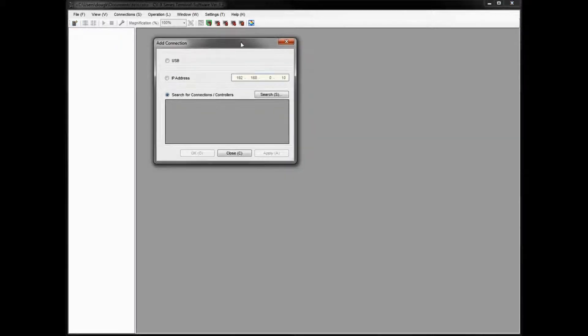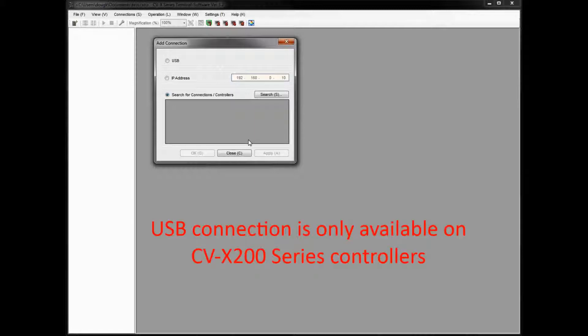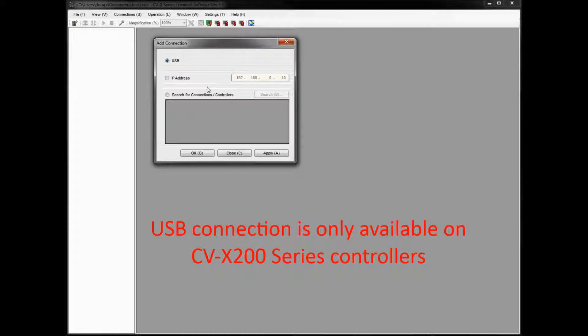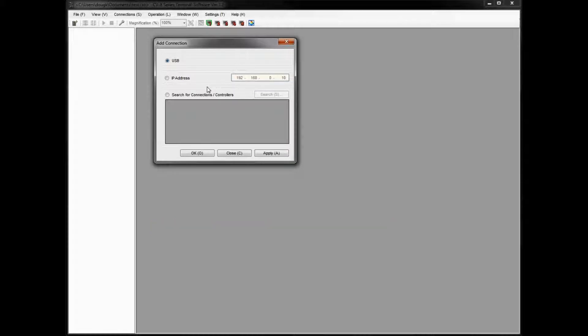If I click this, it'll bring up the Add Connection Wizard. If you're going to use USB connection, which is possible only on the CVX 200 series controllers, you simply select USB. Again, this is only on the CVX 200 series controllers. If you have a CVX 100 series controller, you need to use the Ethernet connection if you want to use the remote desktop function.